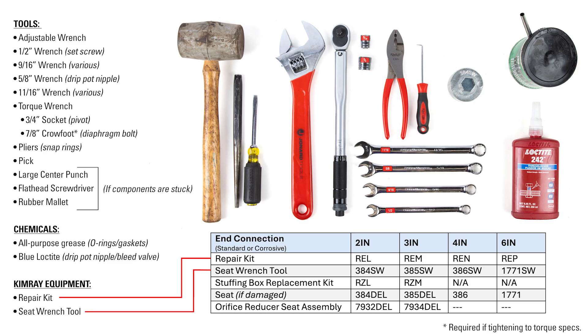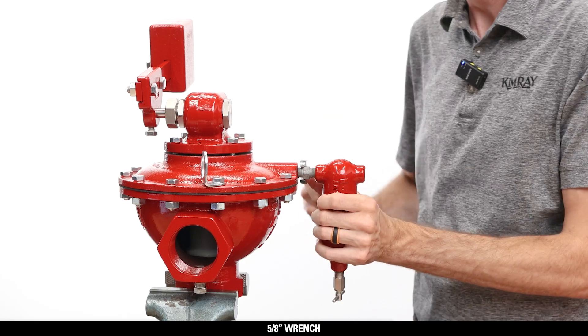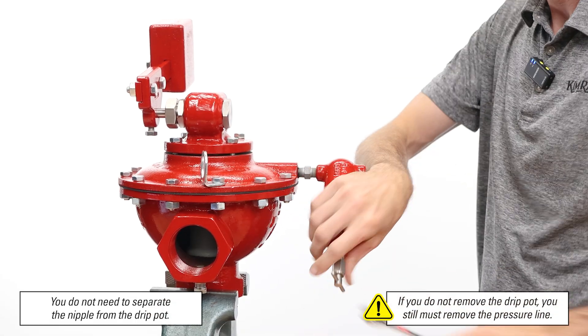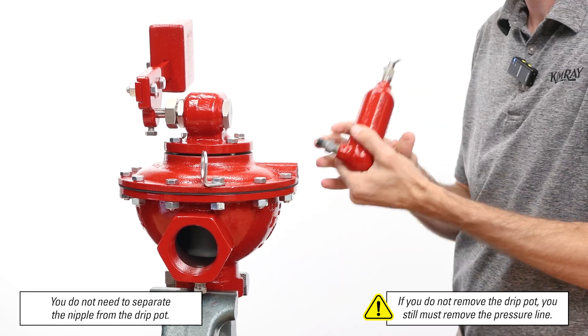This valve can be repaired in line, but if it has to be removed from the piping, start by securing it in a vise. Use a 5/8-inch wrench on the nipple connecting the drip pot to the valve body. There are no repair kit components for the drip pot, but it is important to clean this out when doing maintenance.